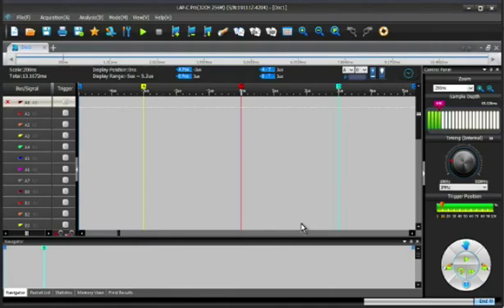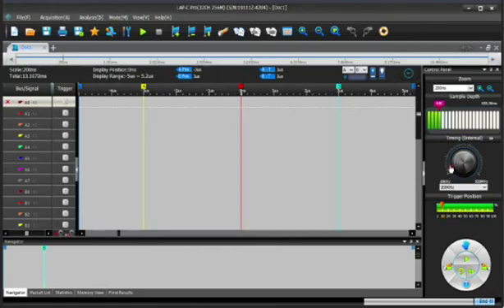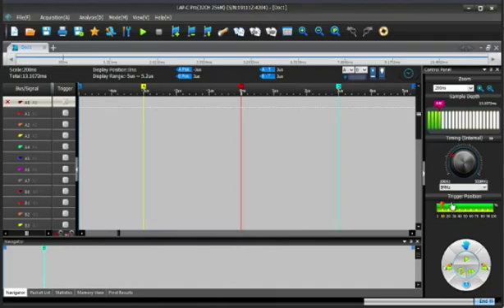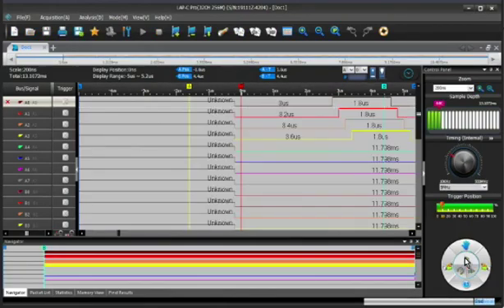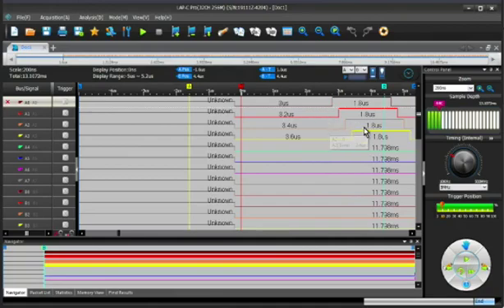So let's look at the user interface. It's pretty intuitive. Everything you need to see is right there on the screen. If you look over to the right, you can control the sample depth very simply, the timing easily either by using the knob or of course you can use the pull down menu. You can set the trigger position anywhere you want it. Let's take an acquisition and see what we see. I just press the capture button and it's sucking the data in and there we have it. I'm driving four or five channels here from a little piece of test equipment I came up with.